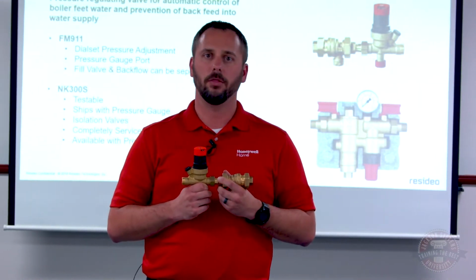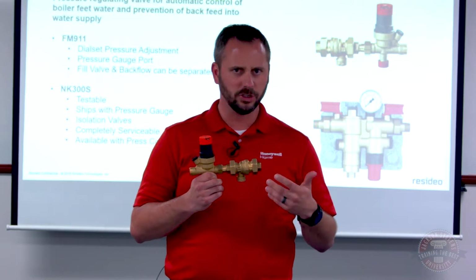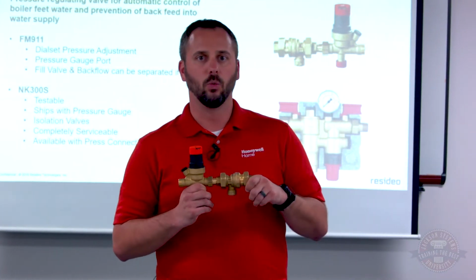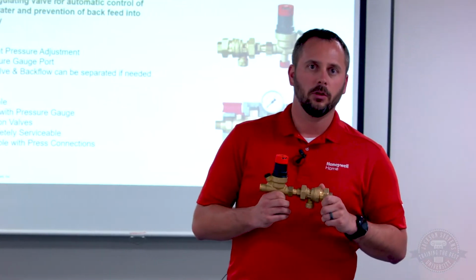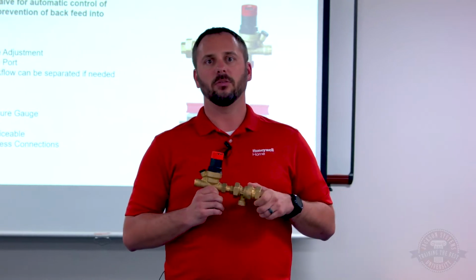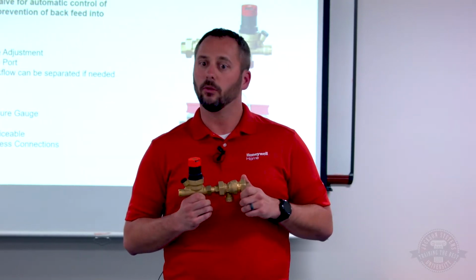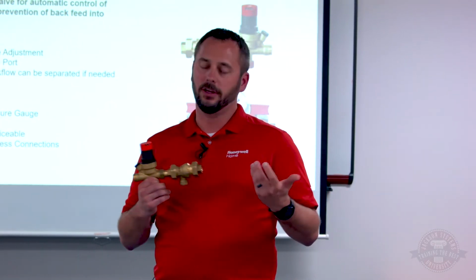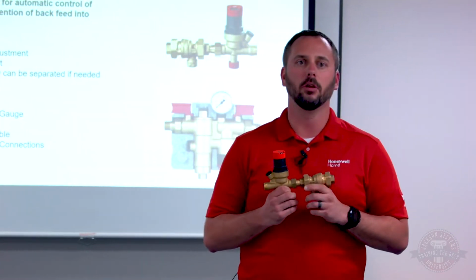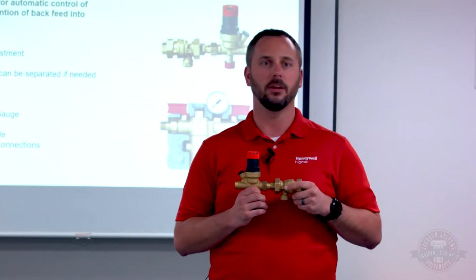So one of the things I always recommend on a hydronic heating system, once you have filled that system and you've let that run through the air eliminator, which I'll go over in a little bit, shut your water makeup off. The reason I say that is you will get some residual air that will purge out down the road. And what that's going to do is anytime you purge out air, you're basically dropping a little bit of pressure out. But a lot of times it's minuscule.